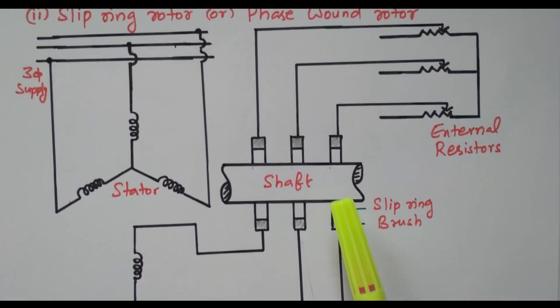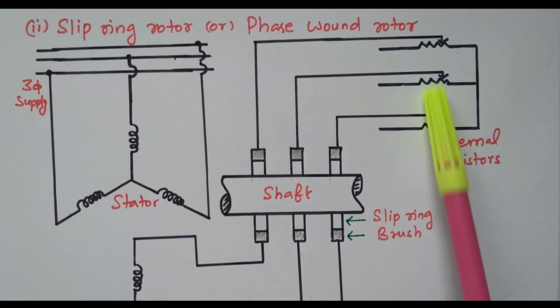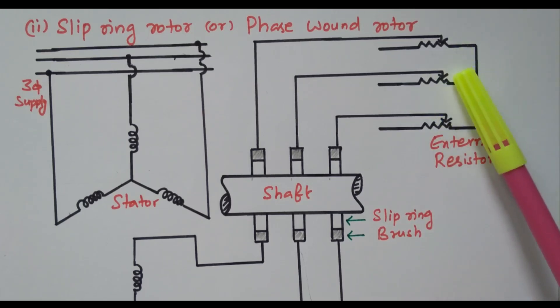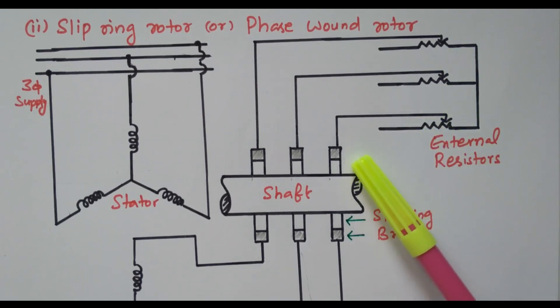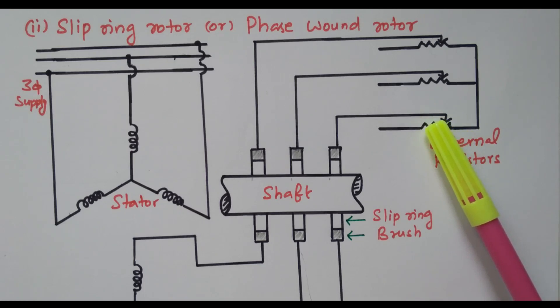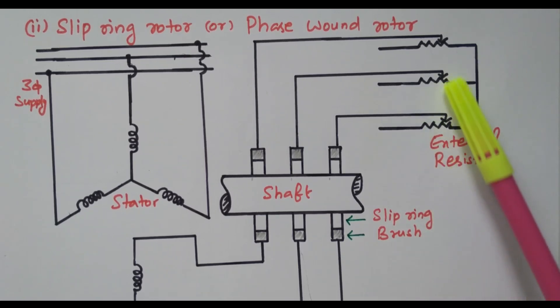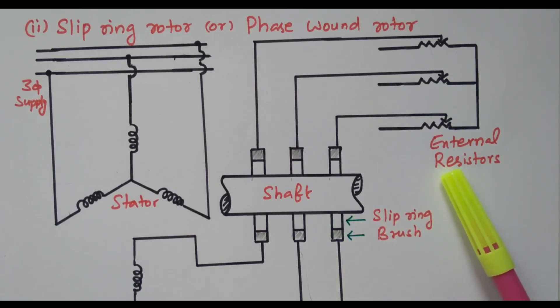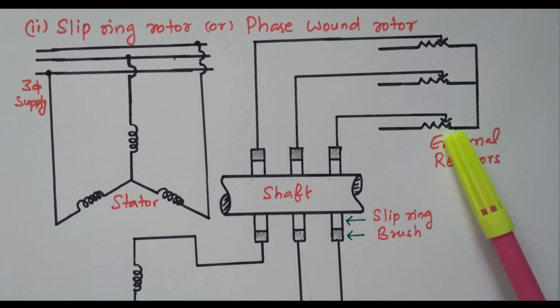At the other end, we can easily add an external resistor. When the resistance is at the maximum position, the current taken by the motor is very low. By slowly reducing the resistor, the current increases gradually, and the voltage and speed also increase gradually. It is possible to add external resistance in this slip ring or phase wound rotor type. This external resistor is used to limit the starting current — that is its main purpose, which is not possible in the squirrel cage rotor.